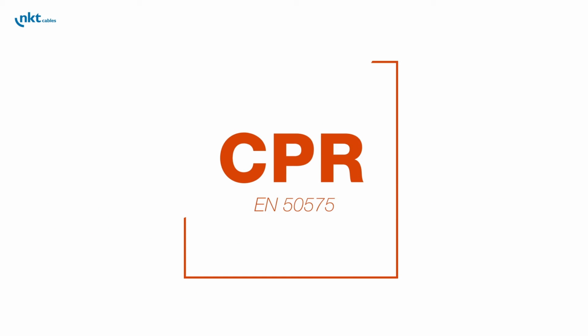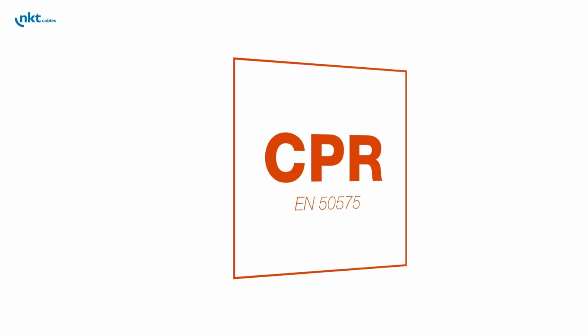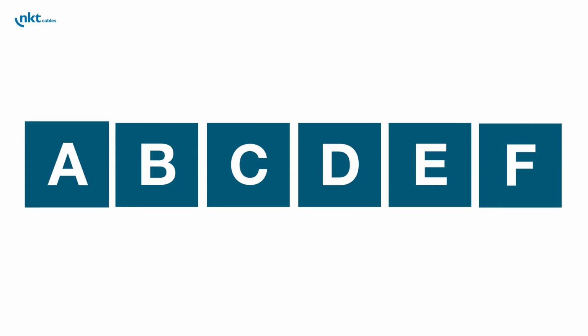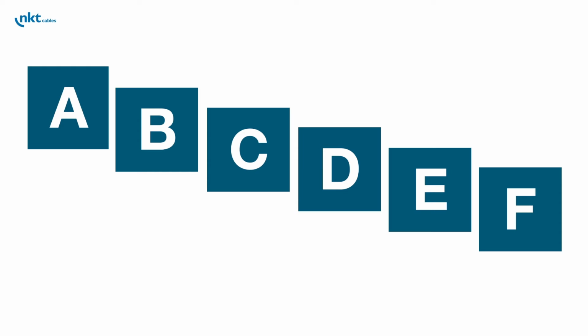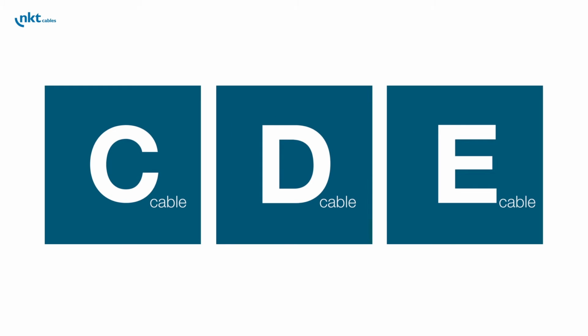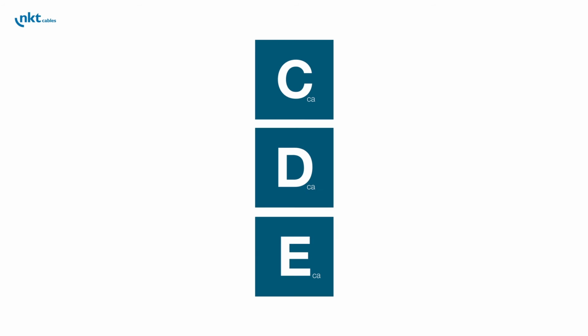The standard replaces the previous fire performance classes with 6 new designations, from A to F, where A implies that the product is non-combustible, and F that the fire performance characteristics cannot be determined. Of these new fire performance classes, C, D, and E will be the classes primarily used for cables. Class E is the lowest level allowing approval for installation in buildings.